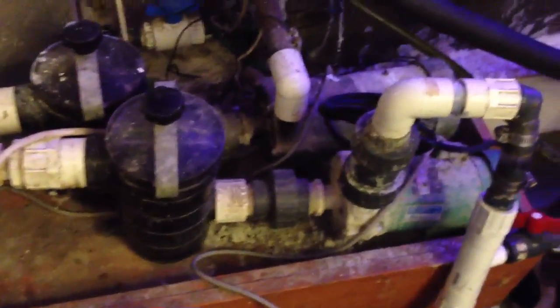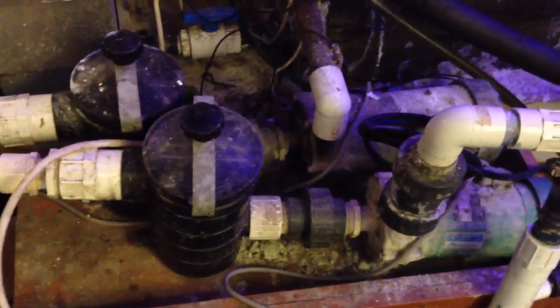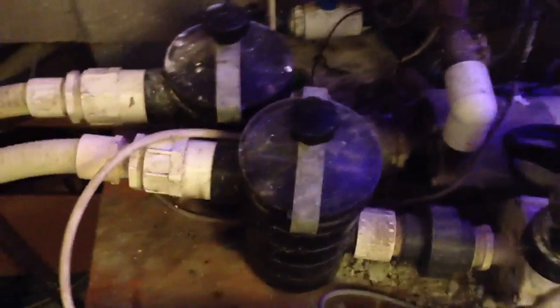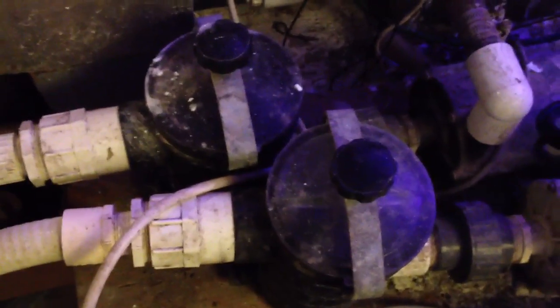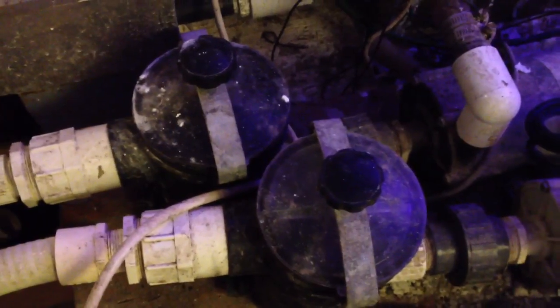As we come around, here are the two primary pumps for the primary loop and the secondary loop. Obviously this is old stuff covered with salt, and it's been running for 20 years. These two pumps have run without any impeller changes because of these two pre-filter baskets that basically make sure there's no sediment or any large object that can pass through the pumps.